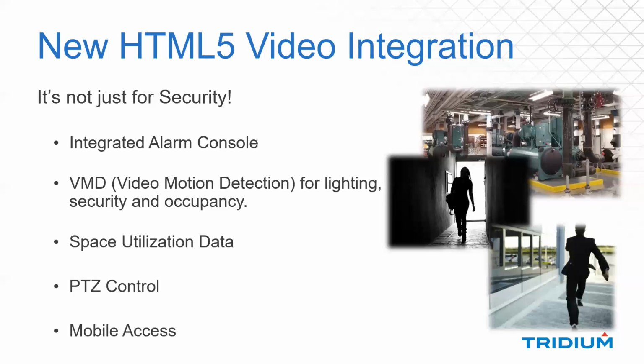HTML5 video integration with Niagara is really an exciting new feature we have. I'll be showing you an integrated alarm console that'll allow you to review alarms directly from your Niagara alarm console. You'll be able to review video associated with alarms. We'll be able to pull in video motion detection alarms from our video system, and these can be used for lighting control, to notify security staff, or even to trigger occupancy. You can even get space utilization by analyzing video motion detection in various spaces to know when there's actually motion in a space and determine when various parts of your facility are actually being used.